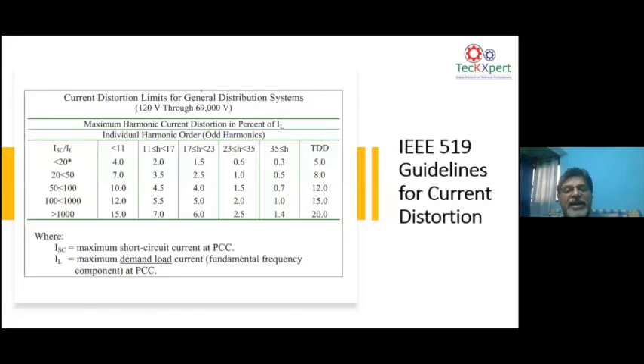Now, if you go into current distortion, you can see for current distortion there is a limit. Current distortion you permit to a user. For example, when I say a strong network or a weak network, if the short circuit level at the point of coupling is very high, then we say the network is very stable. But if your short circuit level is low, then you say the network is not very stable. And the short circuit level again is connected with the impedance.